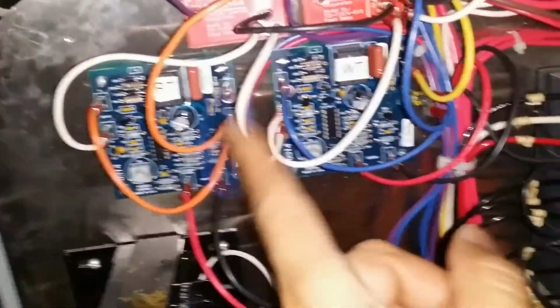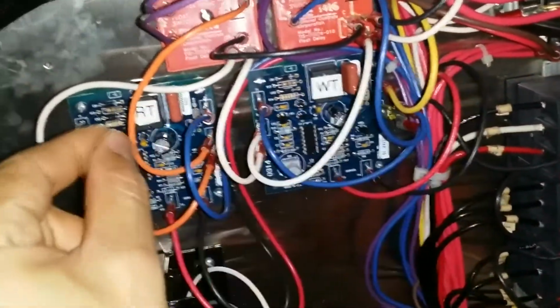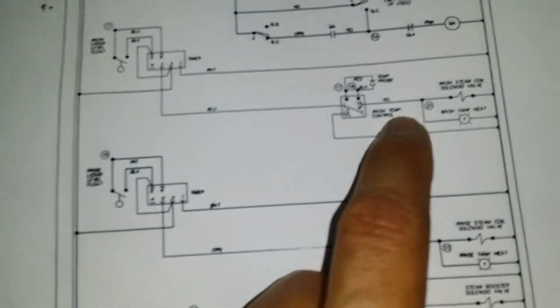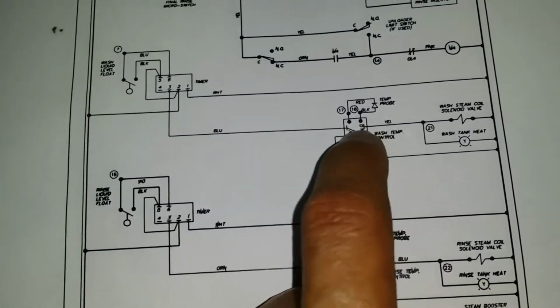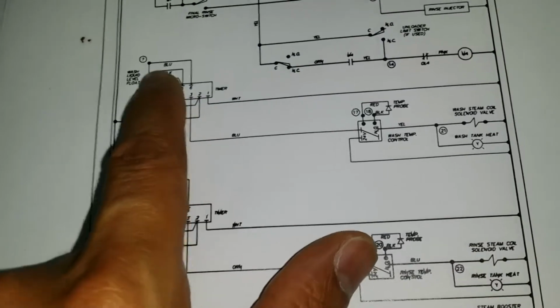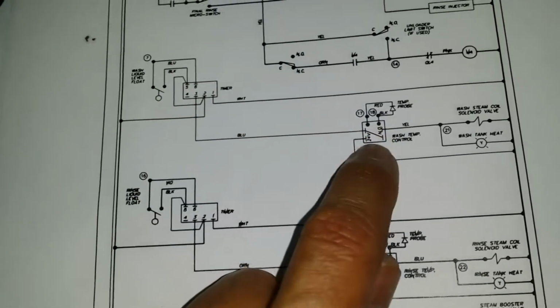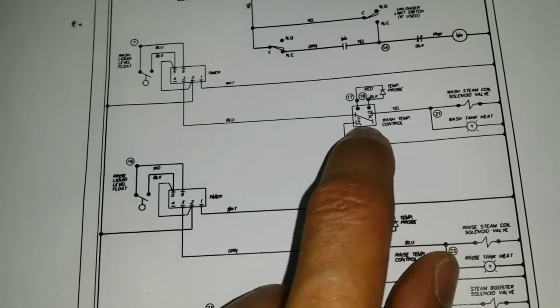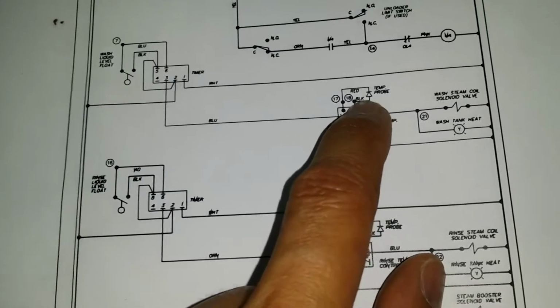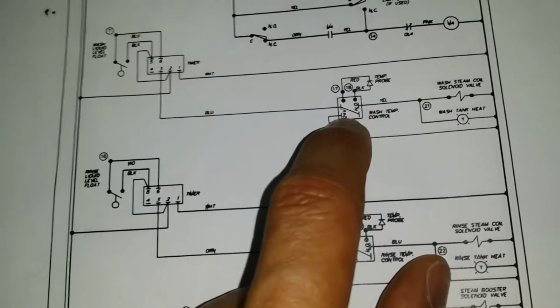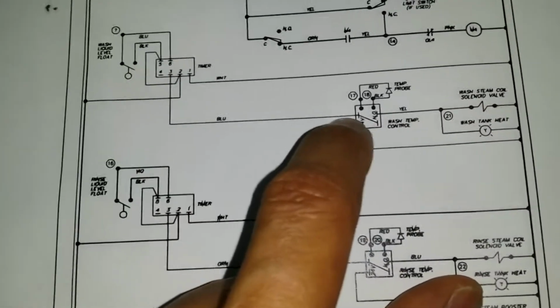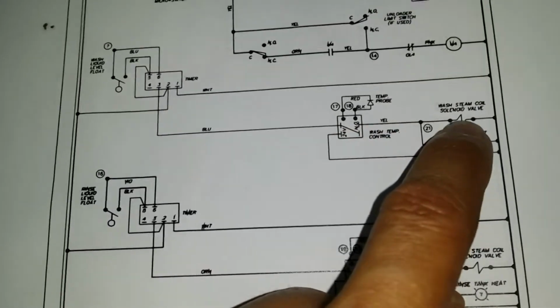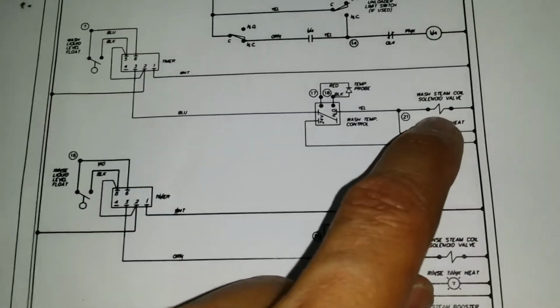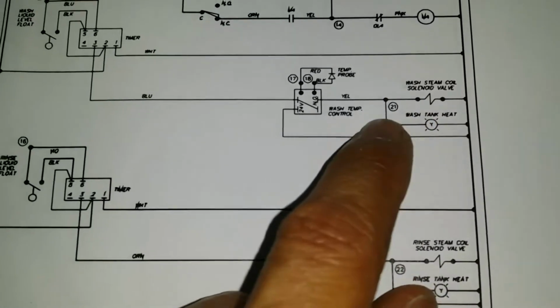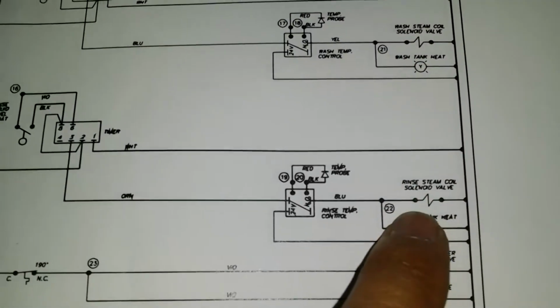So when you're looking at these two over here, we got the yellow wire, and we got our blue wire. Those would be these cables over here. Whenever this one says that there is water in the tank, it will allow power to power this card. And if this card measures the temperature, and decides that the temperature is not correct, it will energize, putting this potential into this point, energizing this solenoid, and therefore the system will start to heat up. This is my wash and this is my rinse solenoid.